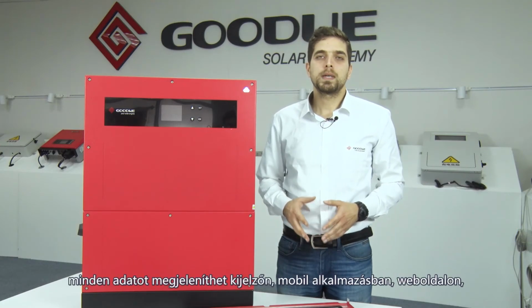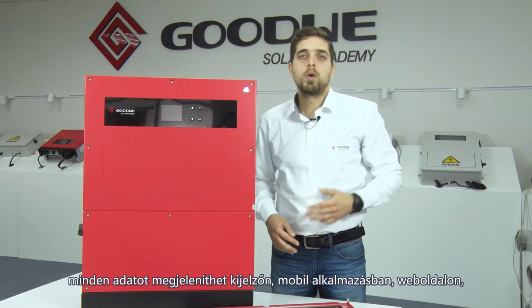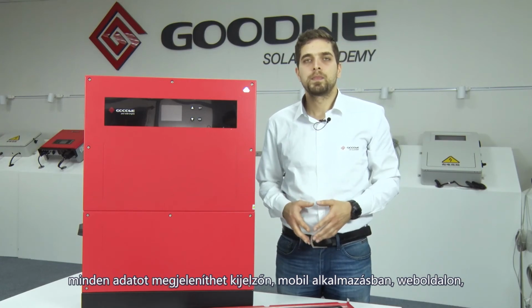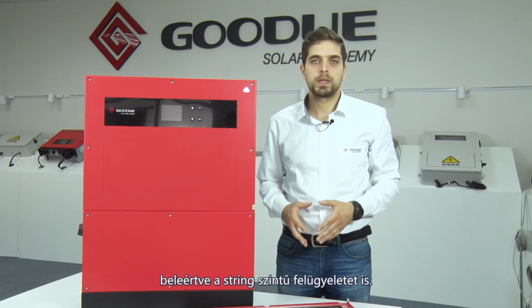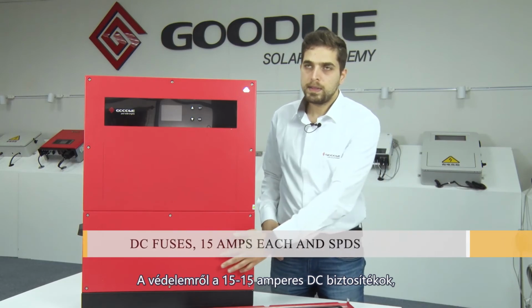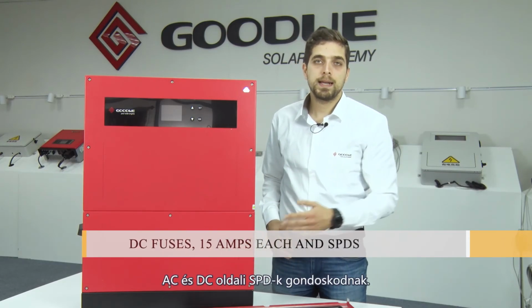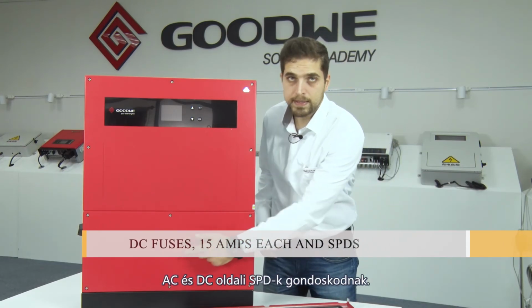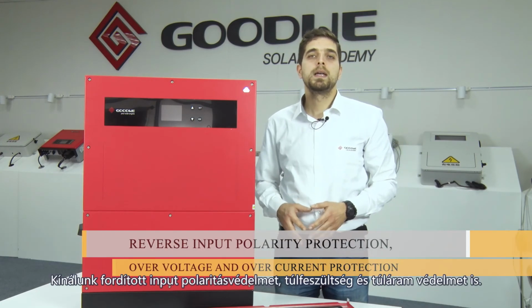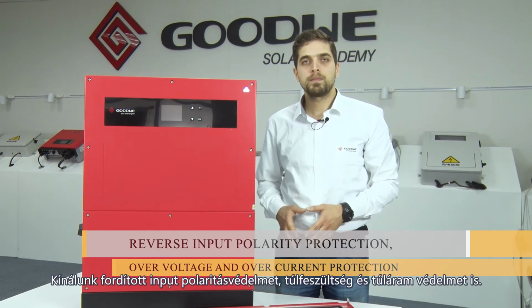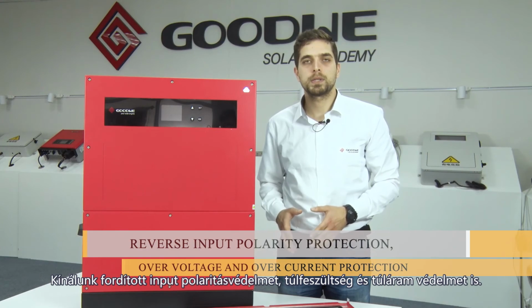For monitoring, you can see all the data on the screen, mobile app and website platform, including string level monitoring. For protection, there are DC fuses, 15 amps each, and SPDs for both AC and DC side. Also, we have reverse input polarity protection, over voltage and overcurrent protection.